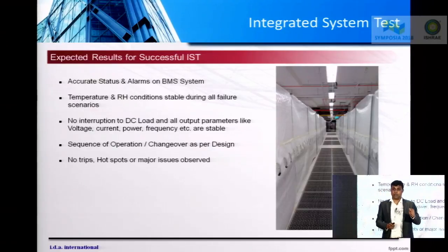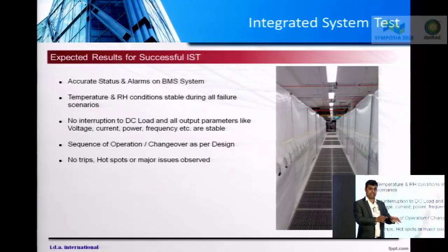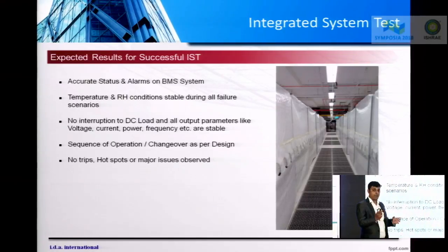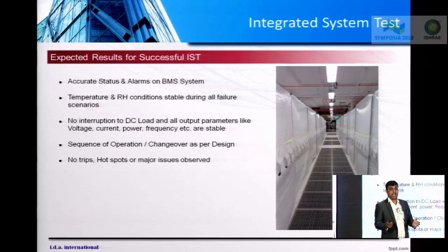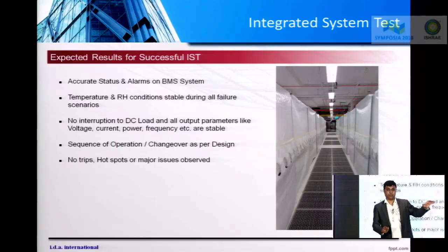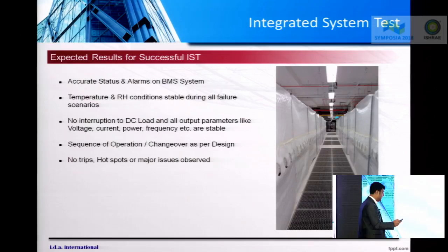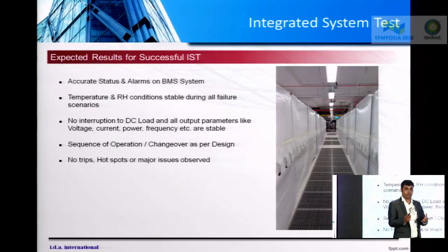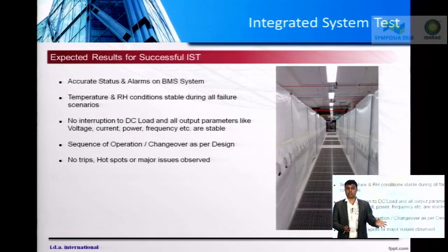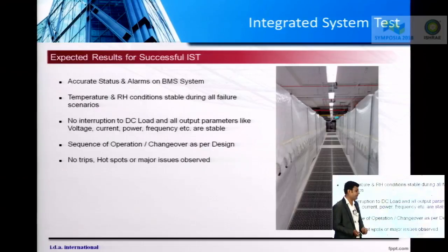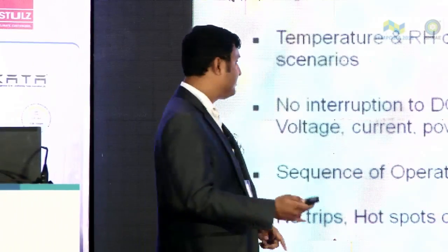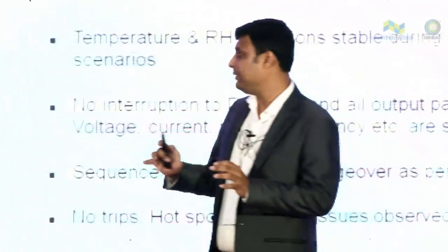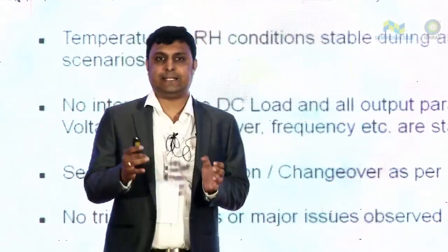We are verifying the temperature and RH conditions throughout the failure scenarios and verifying that they are stable and within the SLA limits. We are checking that there is no interruption at the DC load. No matter what failure you create, the DC load should be intact. For the sequence of operation, we have to verify the logic, the cause and effect, the time settings, etc. And finally, you should have no trips, no hotspots, or any major issue throughout the IST. So that is how we carry out an integrated system test.